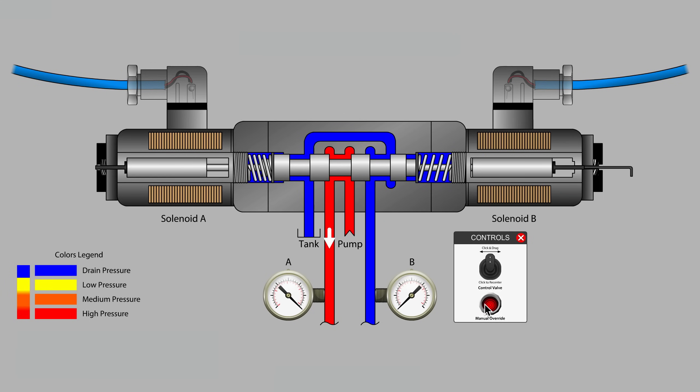Pushing on the mechanical override is a simple way to find out if the internal parts of the valve, namely the valve spool, is still free to move and operating normally. Make sure that when you push the mechanical override that no solenoid is still energized, especially the solenoid on the opposite side.